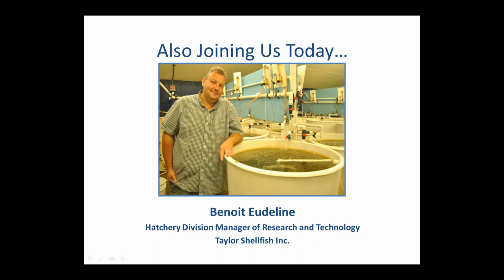So I cannot talk too much about this accuracy and precision, but all I can say is that at the moment, when we look at the calculated pH compared to the measured pH for the Durafet, they are generally very close to each other and within 0.02 if all the conditions are right. And that's a key point, because at times there is a much bigger difference than that between the calculated and measured, which is a sign for us that something is wrong. And as Todd mentioned, generally it has to do with biofouling, so that's a very good indicator for us.